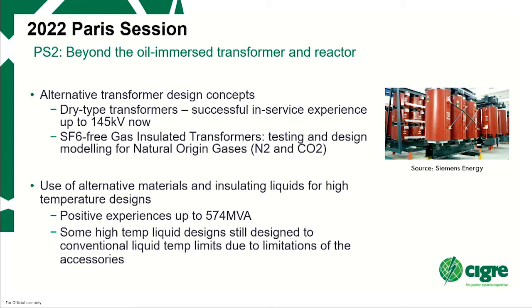For use of alternative materials and insulating liquids in high temperature designs, there's positive experience in installations now up to 574 MVA, but it was acknowledged that some high temperature liquid designs still use conventional liquid temperature limits because of limitations of accessories like tap changers, bushings, and gaskets, so more development work is needed in that area.